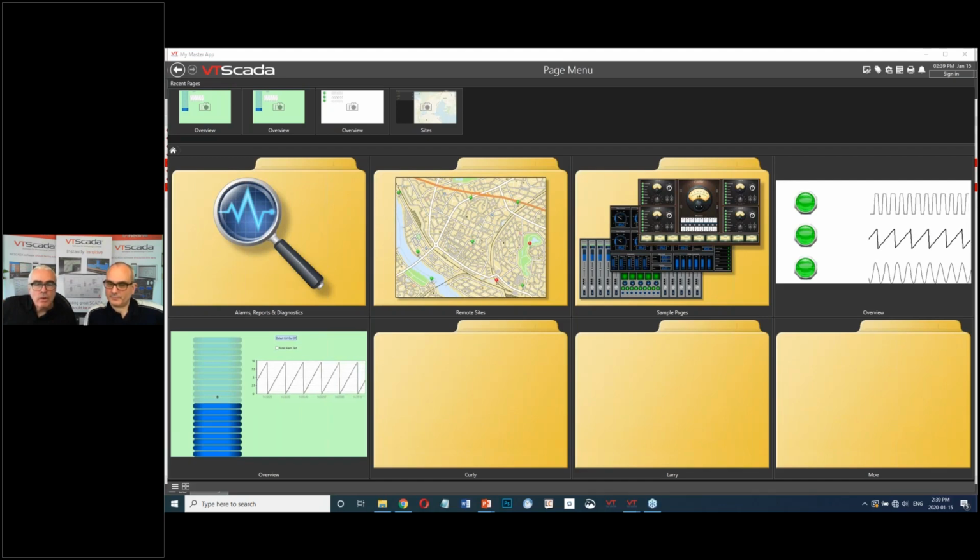The historical data is associated with the application that has the IO tag. So if the IO tag is in the subordinate application, then the history is stored with that subordinate application. If the IO tag is using a driver in a subordinate application, but the IO tag is in the master application, then the history will be stored with the master application. So that prevents duplication and avoids confusion and obfuscation. Gotcha. It's wherever the IO tag is, forever.